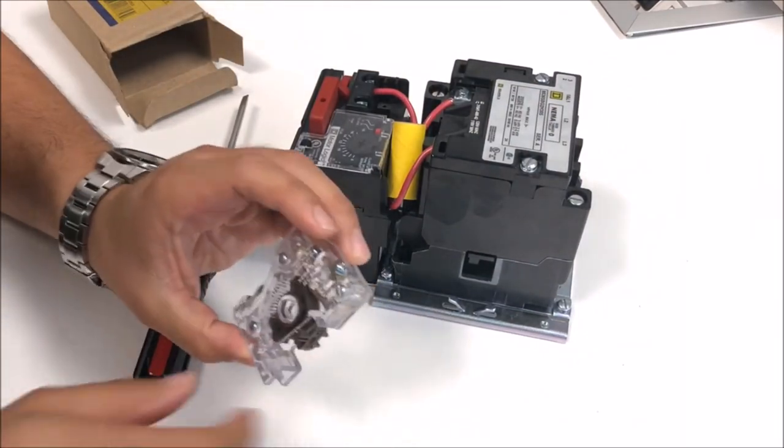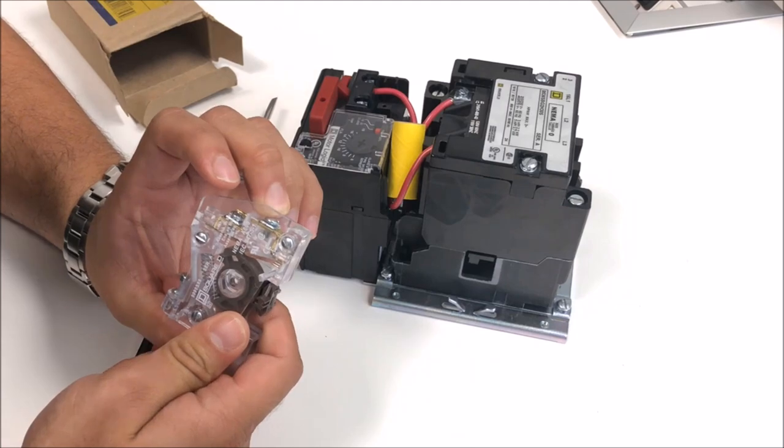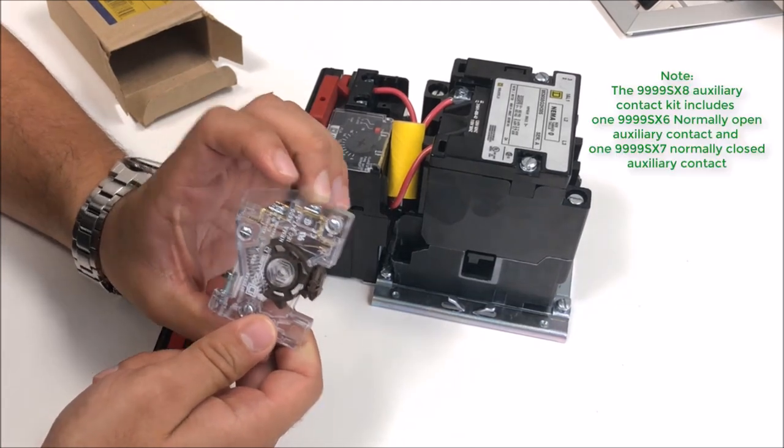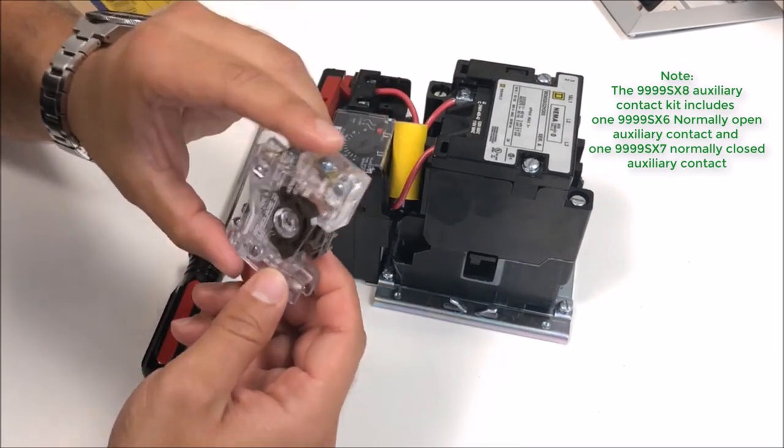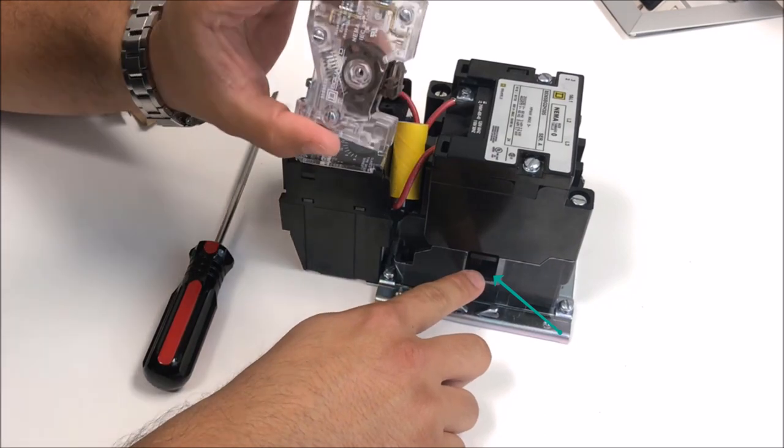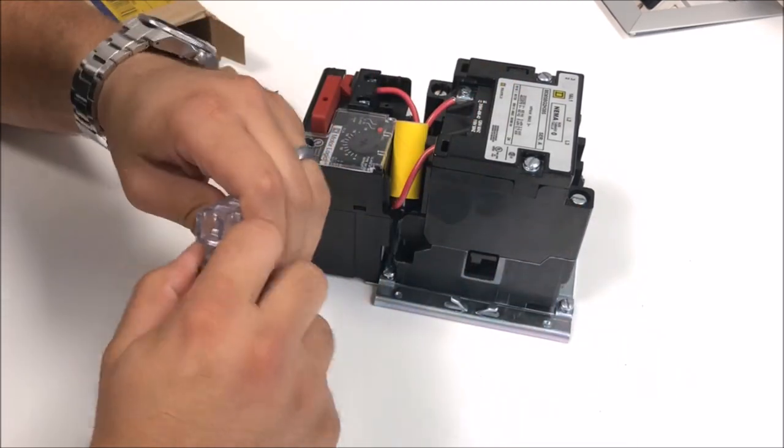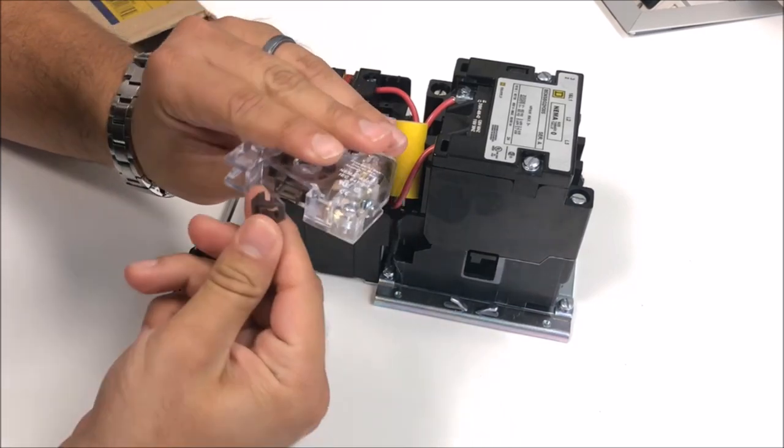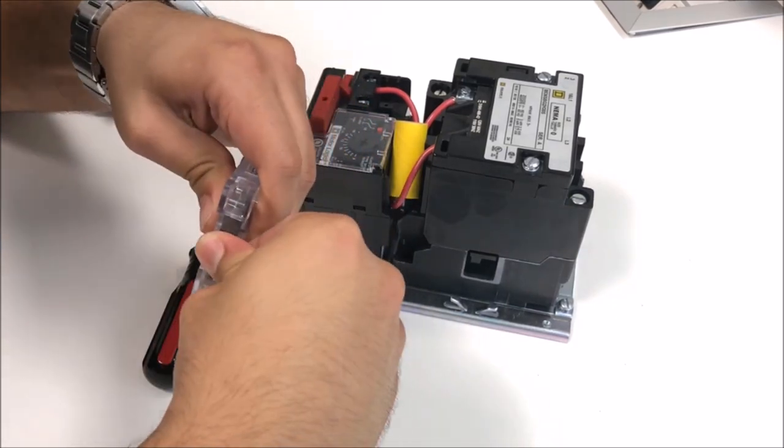Now mount the auxiliary contact. I have a 9999 SX6 here which is a normally open auxiliary contact. These can be mounted on either side of the device. What you're going to do is align this operating lever along with the cavity in the starter itself. These can be removed and positioned in either way to make sure it operates correctly and interlocks with the starter.